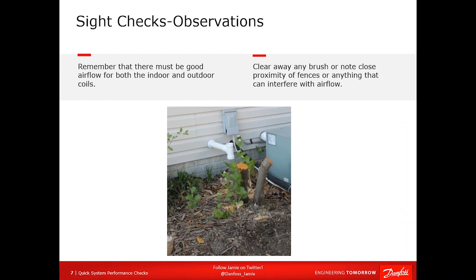Air measurements — indirect indicators include ice. If something's iced up, there won't be airflow through it. Stop fans, dirty filters — if your air filter looks like a sweater. I've seen things as obvious as a stick stopping a fan from turning, or one blade on an outdoor unit that's all wonky. Vegetation is another issue: people love to put stuff around these units without realizing it's hampering performance. You can have a wonderful SEER 16 unit, put a fence around it, and you've turned it into a SEER 10 system because it's going to operate about 25 degrees hotter than it needs to. Always recommend clearing brush around the unit.